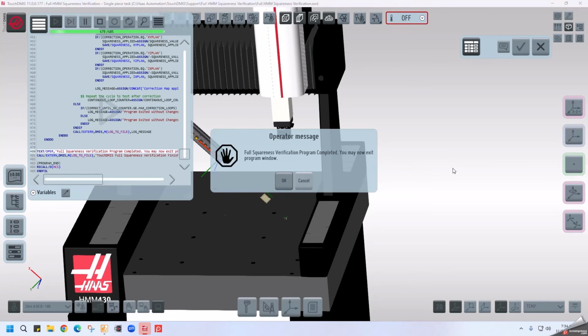Now that the CMM has successfully measured the step gauge in the XZ orientation for position 1 and position 2, you'll see an operator message that says full Squareness verification program completed. You may now exit the program window. Once you see this message, you can click OK, and now the CMM is ready to measure parts.